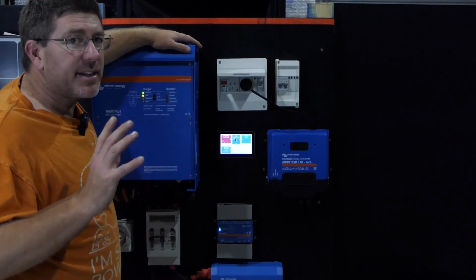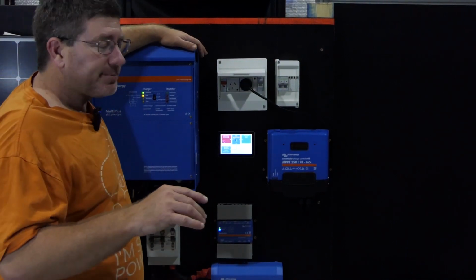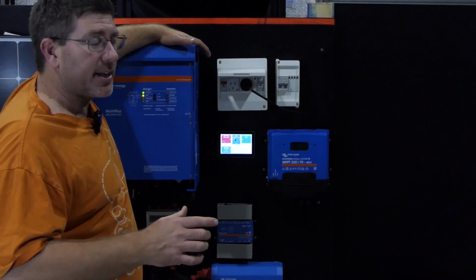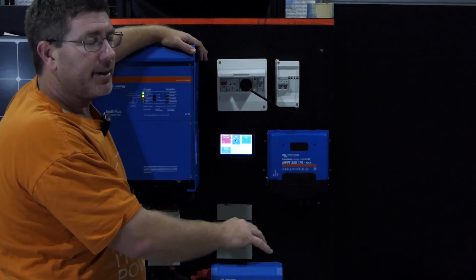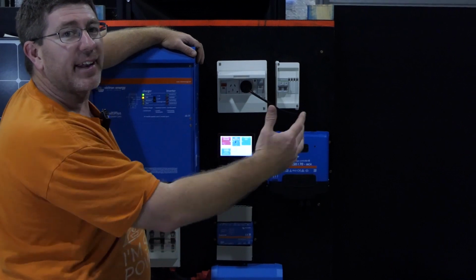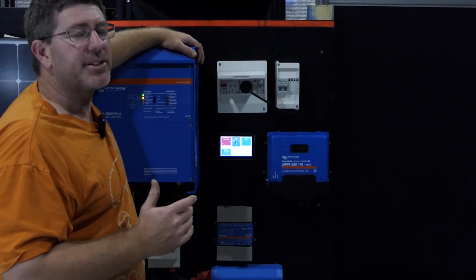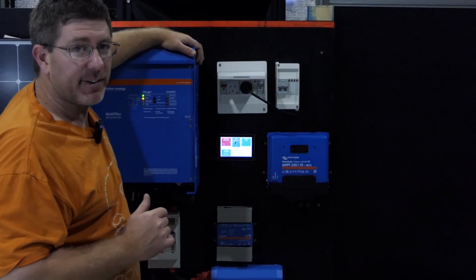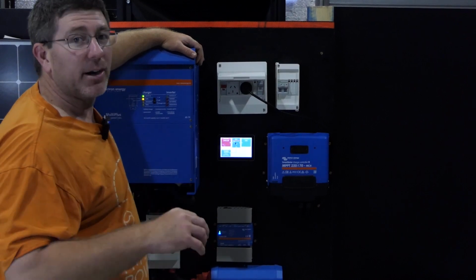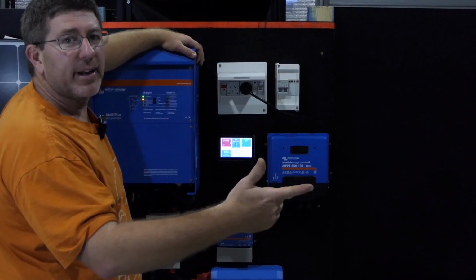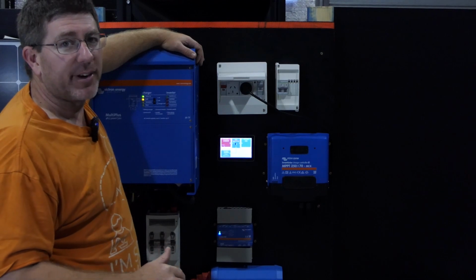Now, the other thing to think about and consider is that when it's raining and it's wet, if you want to charge your batteries and you want to run big loads at the same time, the more loads that you're running, the less it's going to go into batteries. It's really important to think about when you're designing your system that you don't want to undersize your generator and end up going, well, hey, it's raining, I want to heat my hot water, I want to cook with electricity, and I want to do it from a 2kVA Honda. It's just not going to happen.